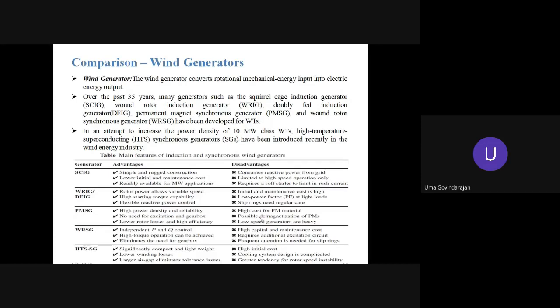One is the SCIG, the squirrel cage induction generator, which is simple and rugged in construction, has lower initial and maintenance cost, and is readily available for megawatt applications. It is very rugged, and to begin with, earlier wind energy harvesting was carried out using SCIG. The disadvantages are that it consumes reactive power from the grid, is limited to high speed operation only, and requires a soft starter to limit the inrush current.